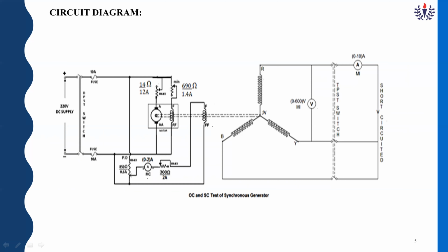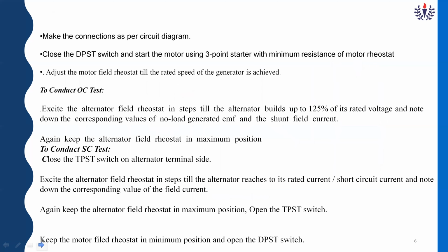And here your TPST should be open for the open circuit test. See the TPST switch, here I am putting a TPST switch, it can be opened. Without the TPST switch also you can perform this experiment, but if I put a TPST switch, I can perform my OC and SC tests in one attempt. So I have used a TPST switch. Now, let me go to the next one. Again, I have to make my alternator field rheostat to the maximum position. Now, how to conduct the SC test?